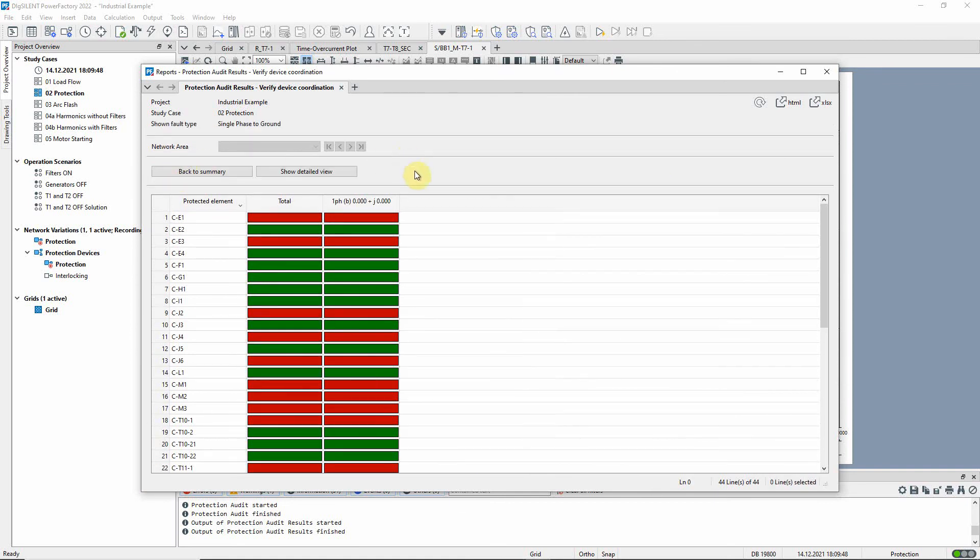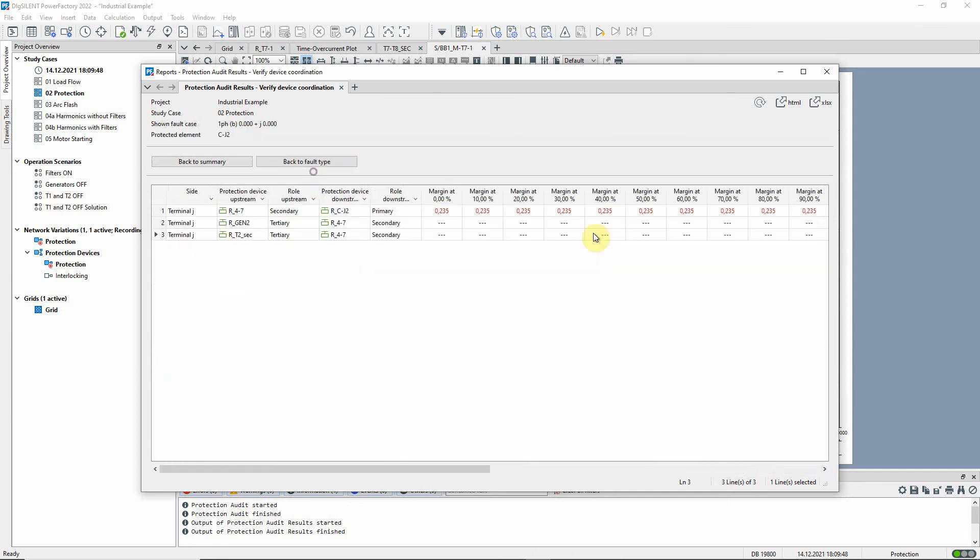Then the results for a particular protected element can be shown in detail. We see that in this case the secondary relay is tripping only 0.235 seconds after the primary, which is less than the specified margin of 0.25 seconds.